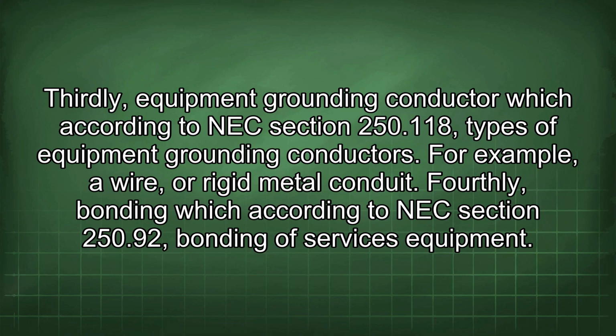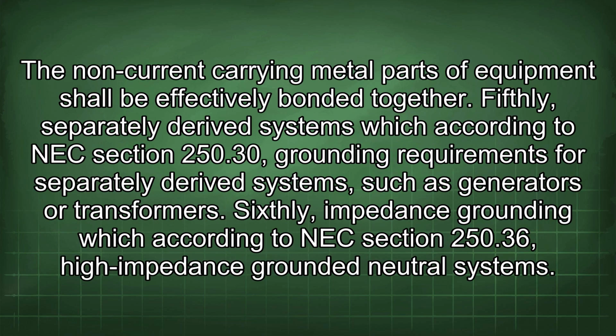Thirdly, equipment grounding conductor, which according to NEC section 250.118, types of equipment grounding conductors. For example, a wire or rigid metal conduit. Fourthly, bonding, which according to NEC section 250.92, bonding of services equipment. The non-current carrying metal parts of equipment shall be effectively bonded together.